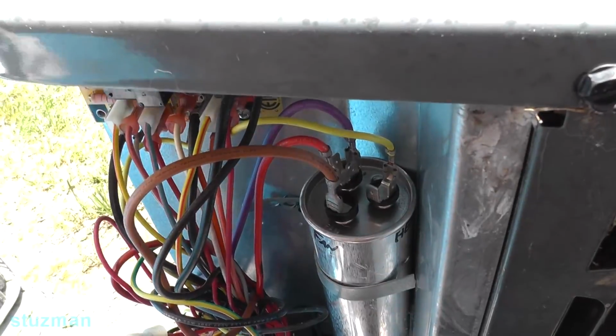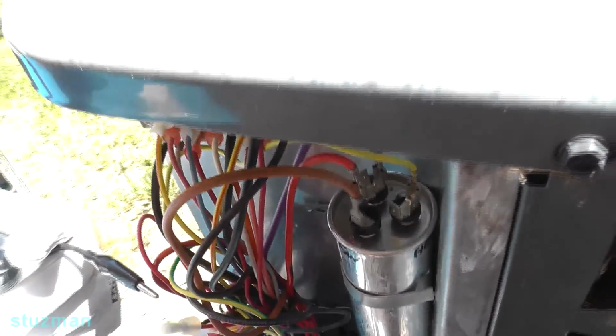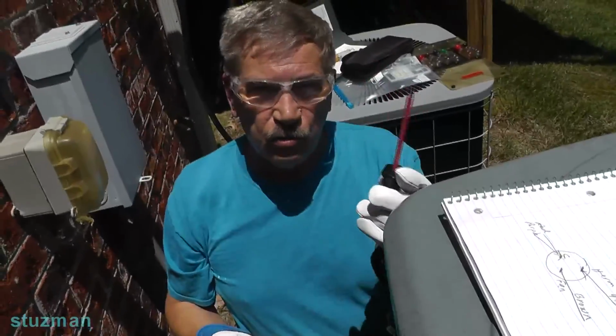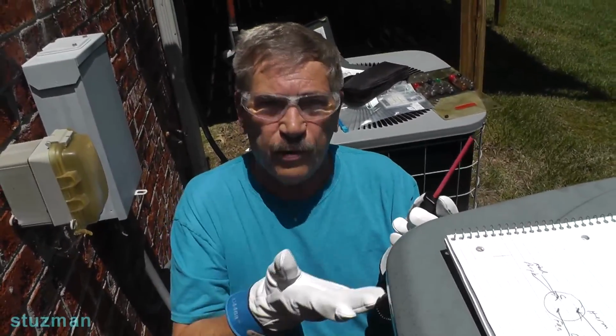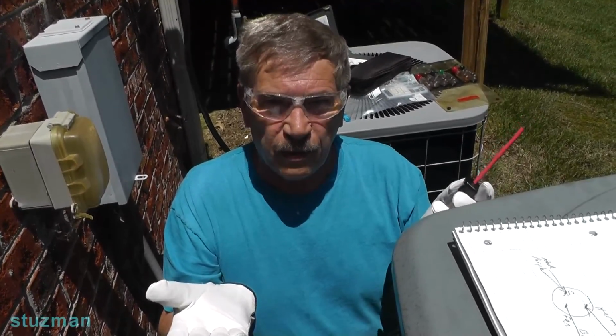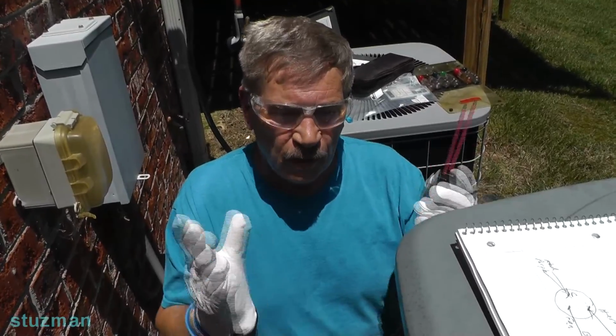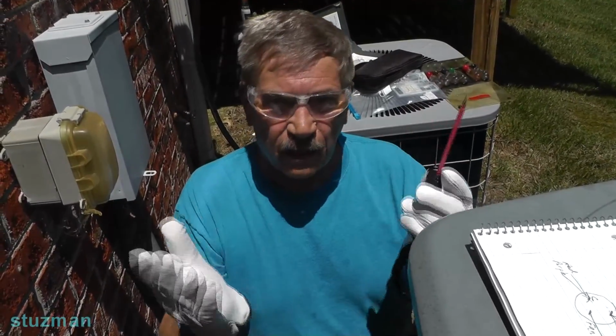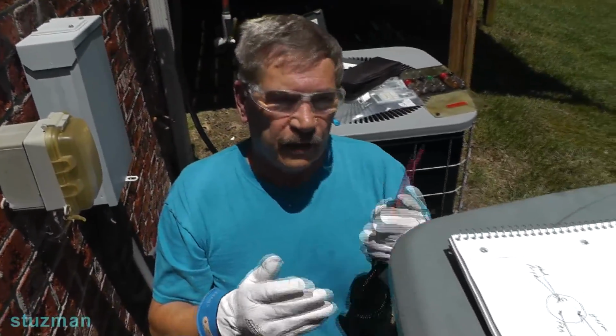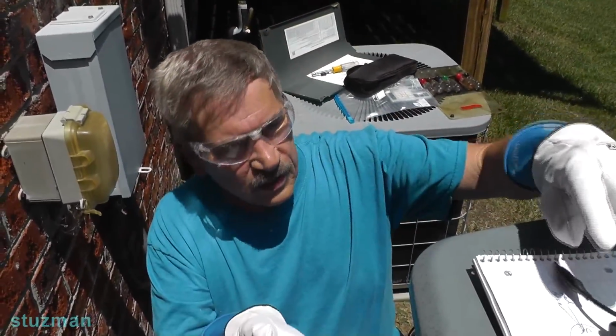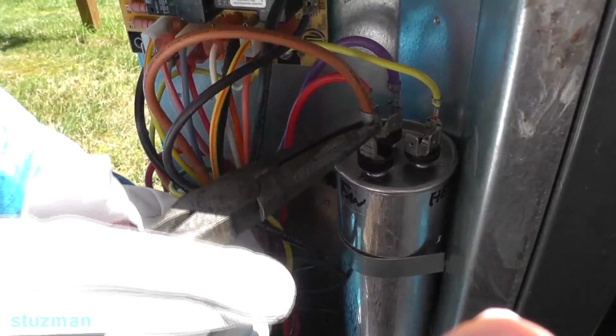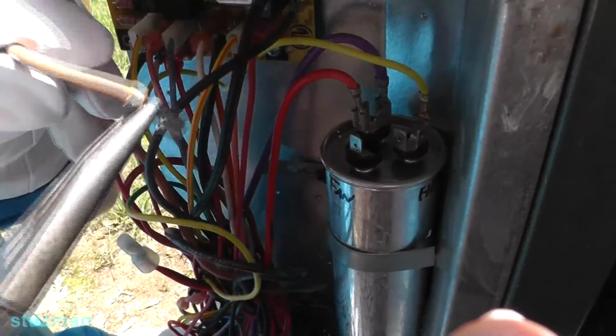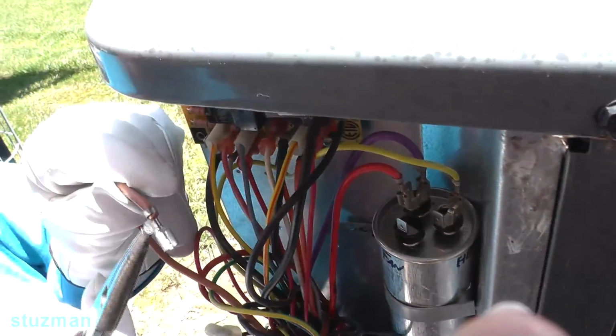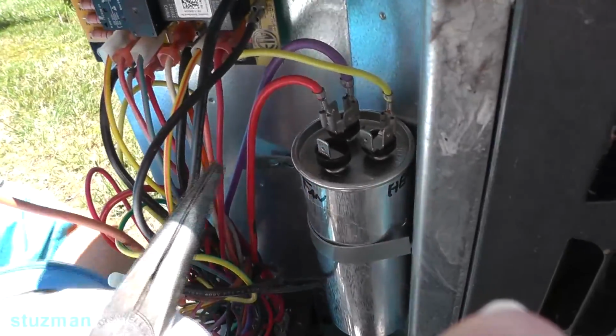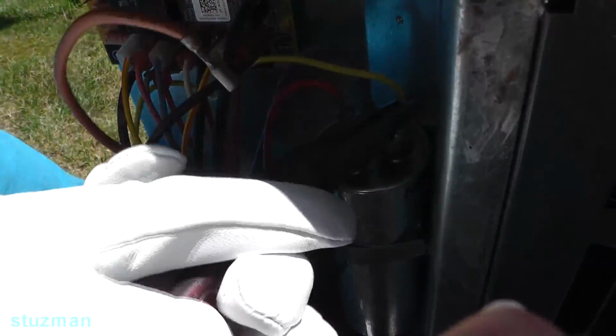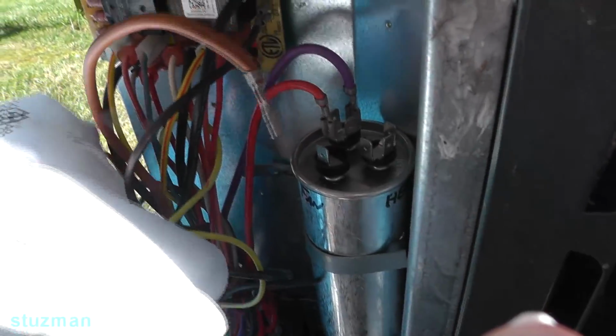Now we'll talk about this resistor and the bleeding off, and probably why it's a good idea to use a device like this instead of taking a screwdriver and jumping across terminals. You see a lot of people do that, but we'll cover that in more detail in the next video. We'll talk about time constants and discharge current and why this is bad. So anyway, now we're going to remove these wires here. When you remove the wires, you want to make sure that this fast-on terminal is secure to the terminal. You don't want it to be loose. You can tell that when you're pulling it off.